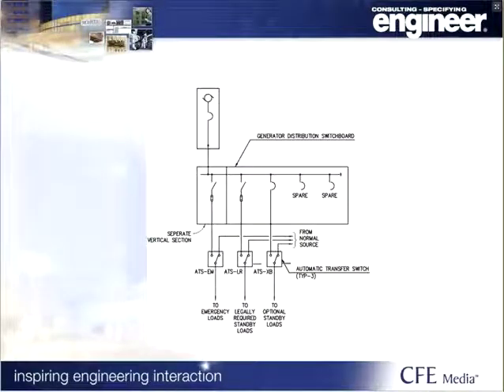Here we're looking at the same generator backup system from earlier. I have highlighted the separate vertical switchboard section for the emergency system. This is required to comply with NEC 700.10(B), which requires wiring to be installed in separate raceways and enclosures. The legally required and optional standby automatic transfer switches require control wiring back to the generator control panel for selective load pickup and shedding to ensure that the generator capacity is there for the emergency system per code.